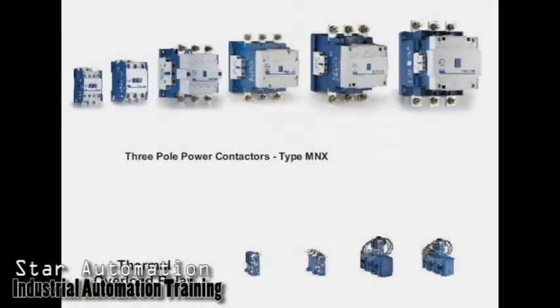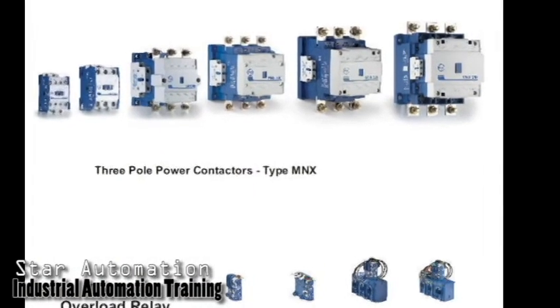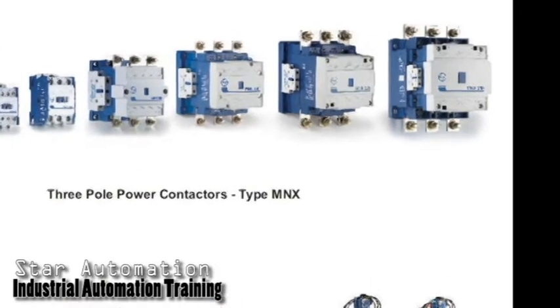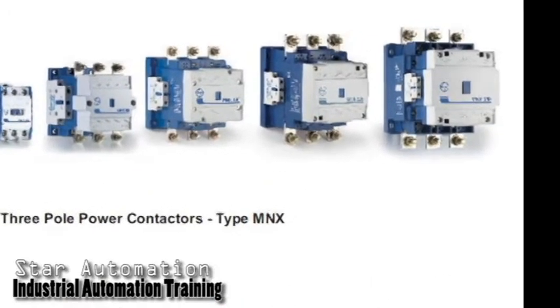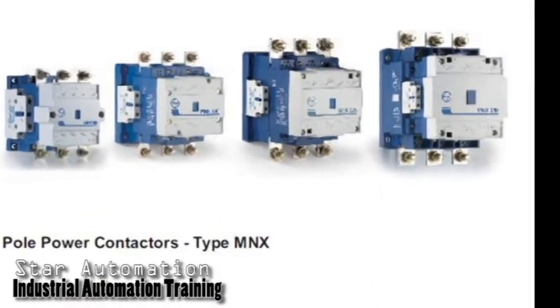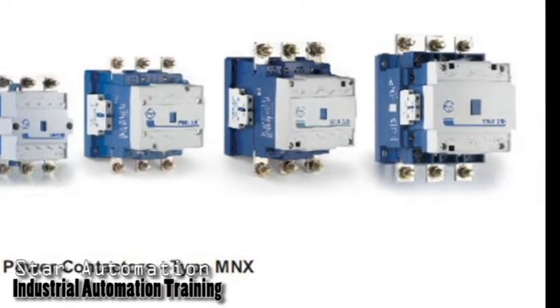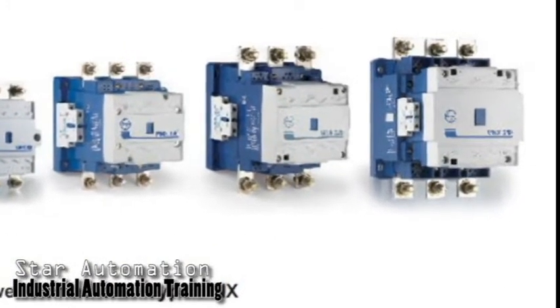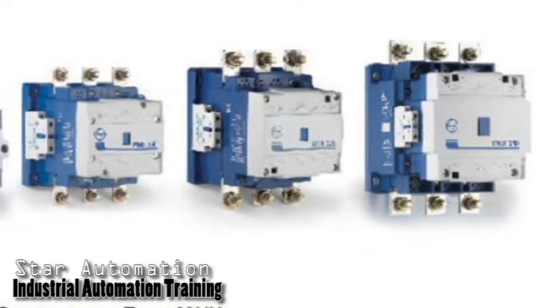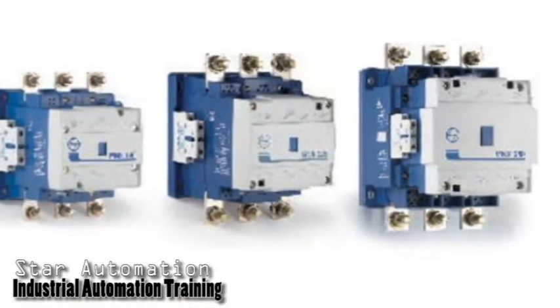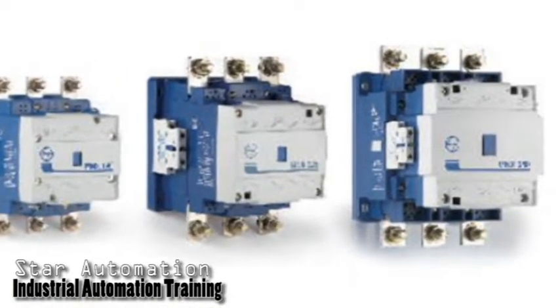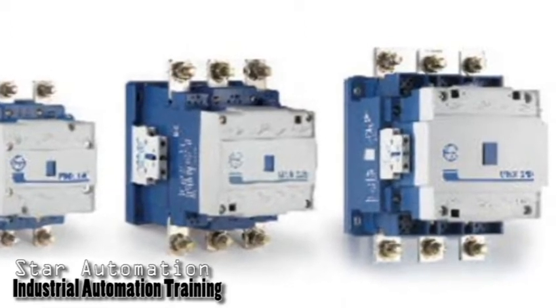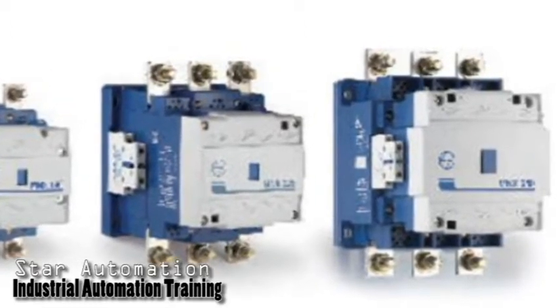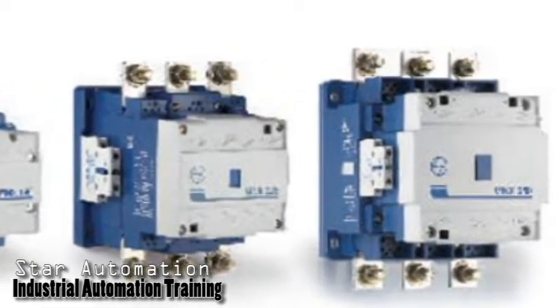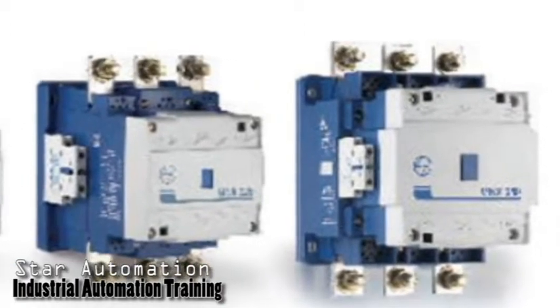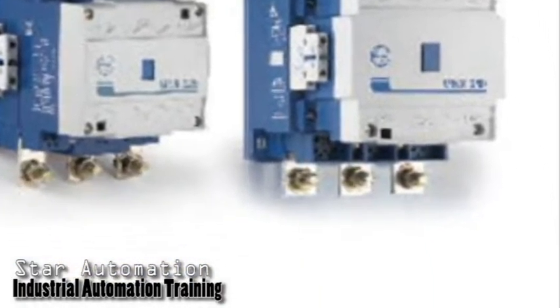A contactor is an electrically controlled switch used for switching an electrical power circuit, similar to a relay except with higher current ratings and a few other differences. When a relay is used to switch a large amount of electrical power through its contacts, it is designated by a special name, contactor. Contactors typically have multiple contacts, and those contacts are usually normally open, so that power to the load is shut off when the coil is de-energized.